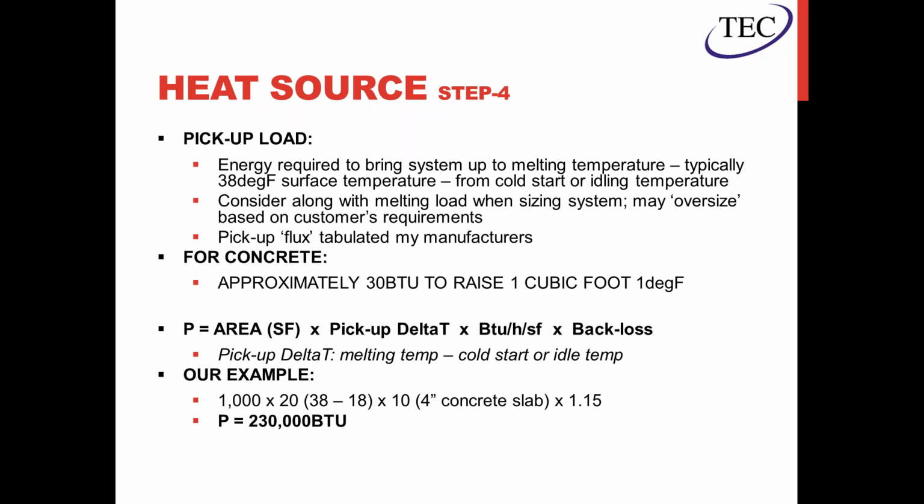So if you're trying to do this for a residence or a non-critical area, the pickup is a little less critical because you're able to allow for more time for it to melt. If it needs to be ready at the second the snow starts, like a helicopter launch pad or whatnot like that, then you want to look at idling and maximizing your heat source for pickup. But we will do an example here so you know what to look for.